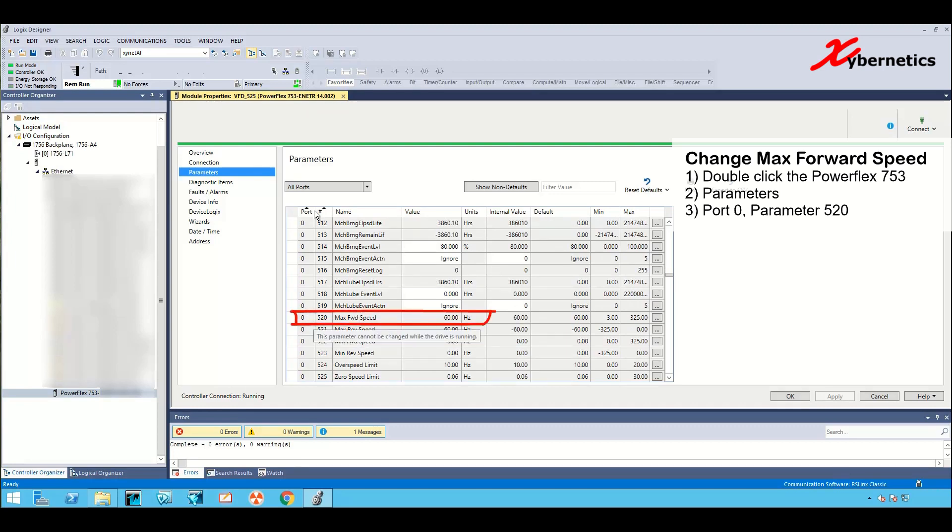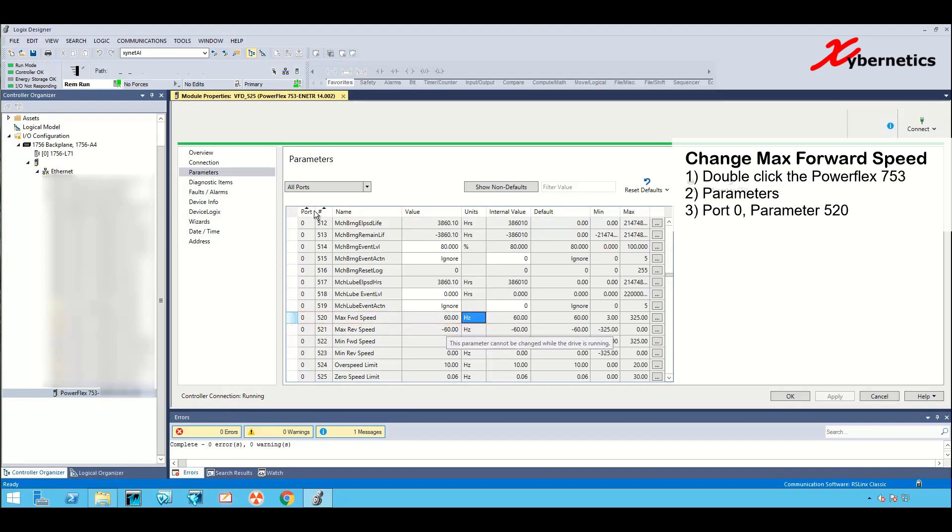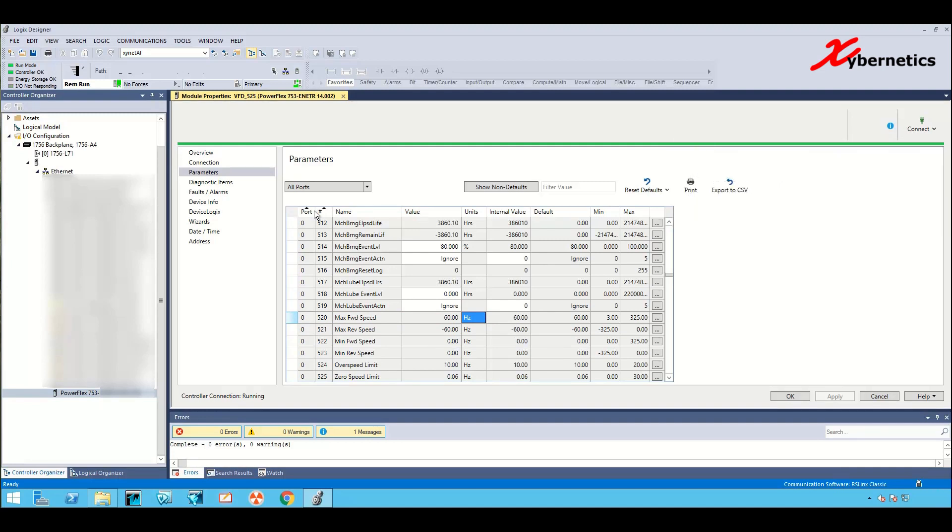The forward frequency right now is set to 60 but you cannot change it. It's been grayed out. It's mainly because the drive is active and running. Before you can access this parameter to change it, you're gonna have to stop your VFD.